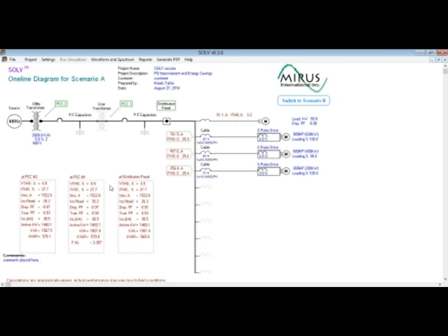Note that we didn't change the per unit impedance value of the transformer, but by decreasing the size of the supply transformer, we affected the short circuit capability of the system, and the short circuit current to load current ratio, ISC to I load, was lowered from about 50 to 26.2. Therefore, it is important that the actual source impedance and the ratio of short circuit current to load current is taken into account when doing harmonic analysis.